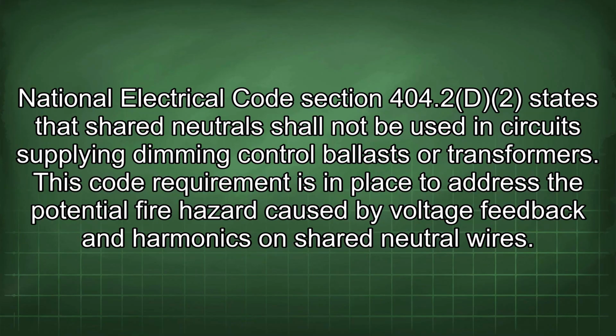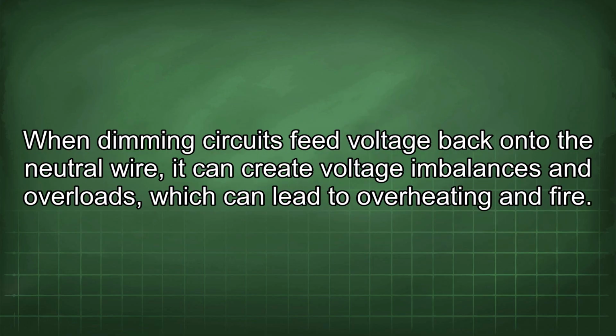National Electrical Code Section 404.2 states that shared neutral shall not be used in circuits supplying dimming control ballasts or transformers. This code requirement is in place to address the potential fire hazard caused by voltage feedback and harmonics on shared neutral wires. When dimming circuits feed voltage back onto the neutral wire, it can create voltage imbalances and overloads, which can lead to overheating and fire.